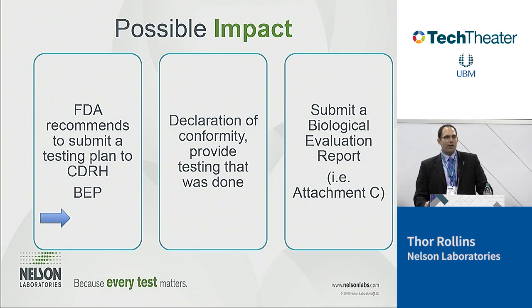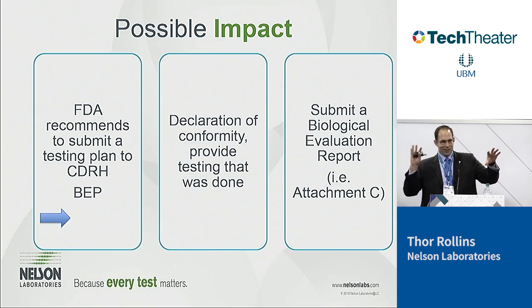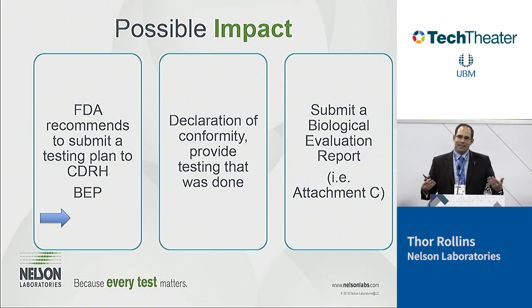If you are declaring conformity, you have to provide that testing was done before on that device. Once again, that is easily done with a device you make yourself, not so easily done with a predicate. And this is the reason why the FDA put this in here: a lot of the testing requirements have changed. We talked about cytotoxicity changing on its extractions. There are some things in the test methods that have changed. So the FDA wants to make sure that the predicate device you're claiming has similar testing to your device, so you're going to have to make that kind of declaration.